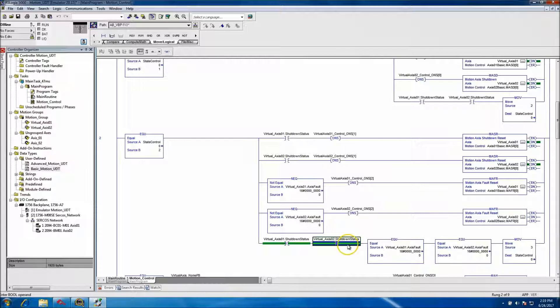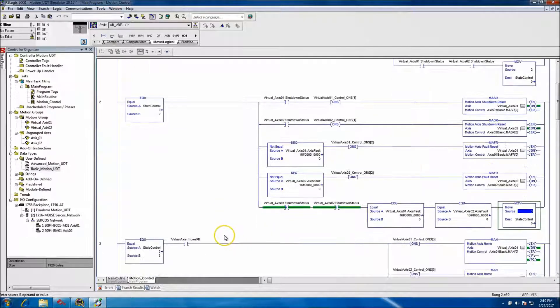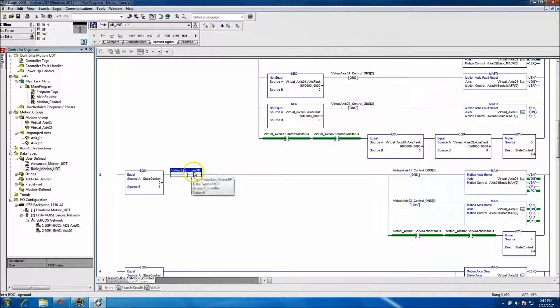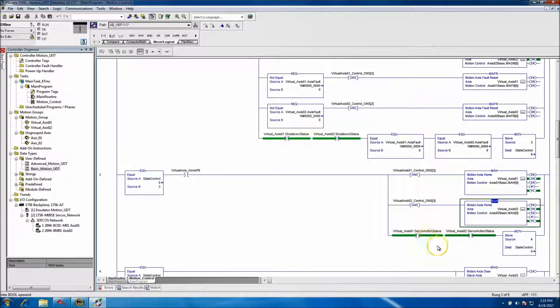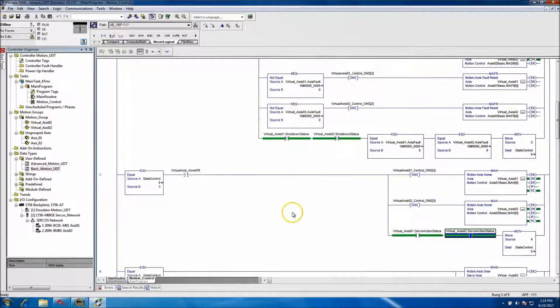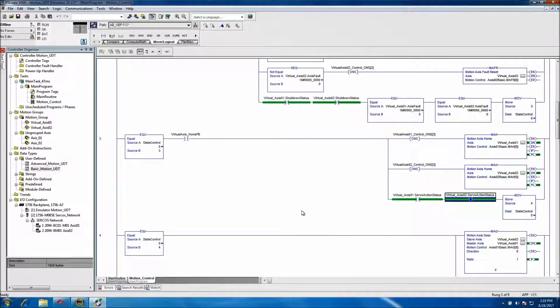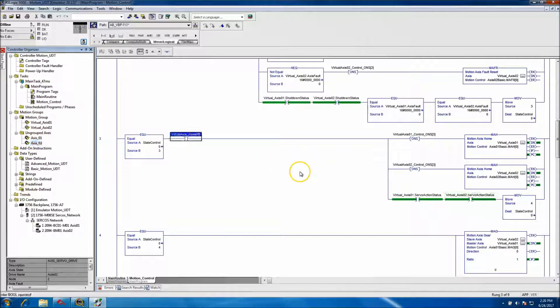To verify there are no faults and the axes are no longer shut down, we index to state 3. If the virtual axis home push button is pressed, it issues a home command. With a virtual axis under emulation, you cannot issue an On command, so you basically just home it, which cuts it off at that point. With a physical device you can home it or simply turn it on and off.